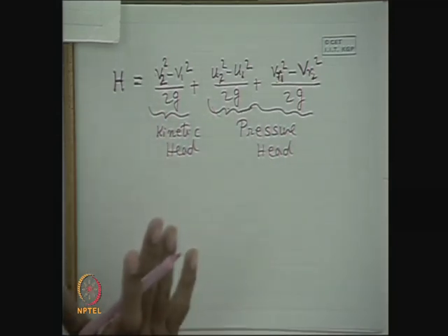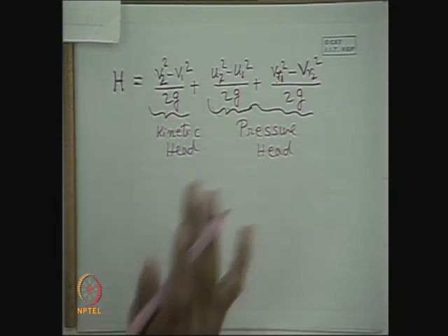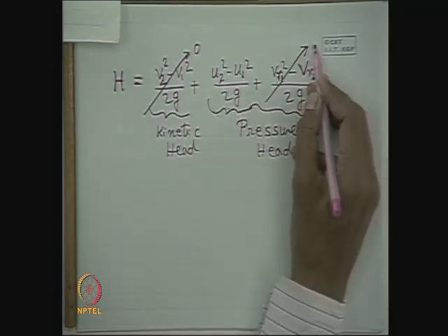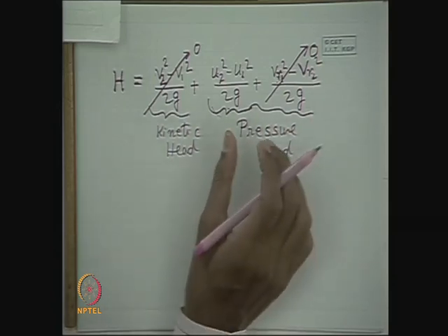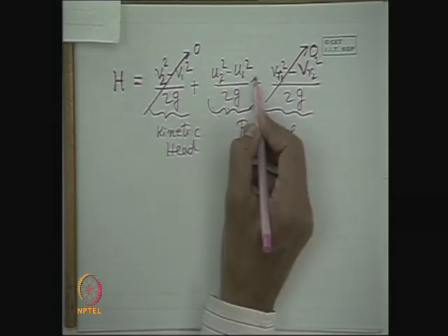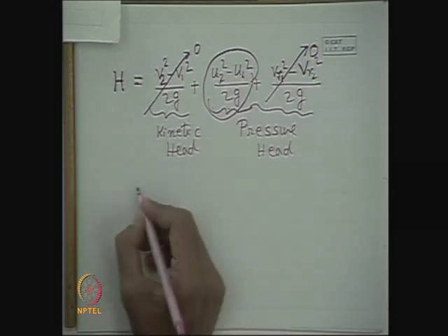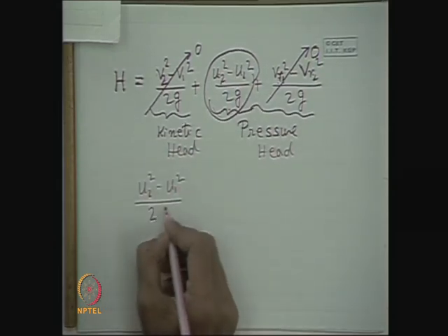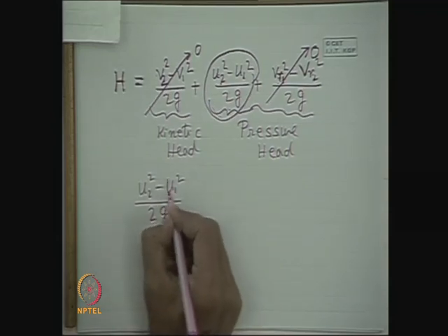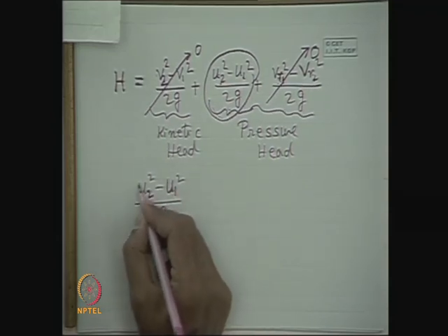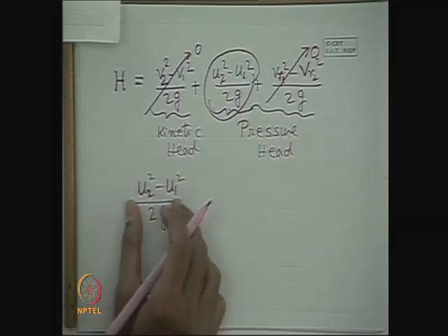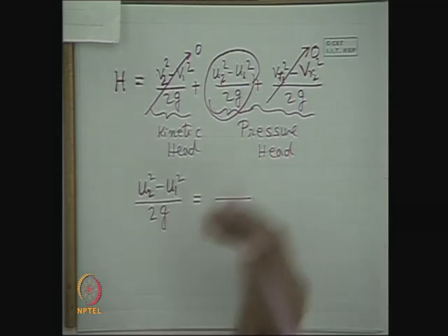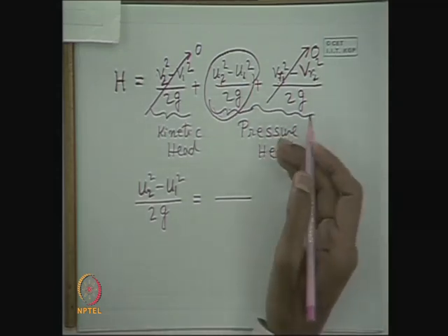Now, when a pump just starts working, at that moment we can neglect these two parts because the velocity has not yet been established. So, at the onset of the start, the pump has to develop only this centrifugal head. Therefore, in this problem, we will equate that the pump dimension and its rotational speed should be such that at the start, the centrifugal head is the only head being developed while these two terms are zero. That must be sufficient to overcome the friction and the static lift.